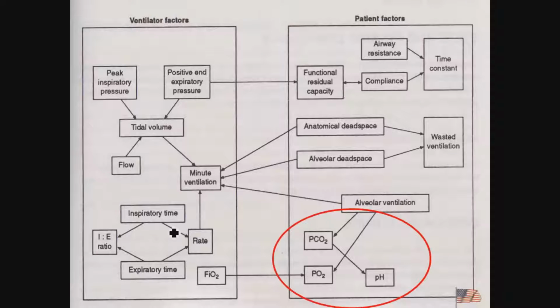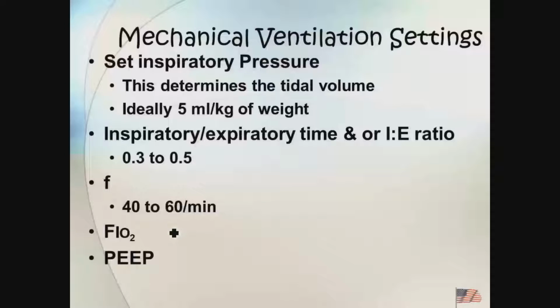So I want to alter my blood gases, and I'm going to do that by altering minute ventilation to control my CO2. We don't set tidal volume typically on infant ventilators. It's usually not something which is controlled by tidal volume, because we don't have a set tidal volume now. We're using a different type of ventilator, a pressure-based ventilator. And we can also use the rate to alter the minute ventilation. It's our primary mechanism by which we're going to control CO2, by controlling alveolar minute ventilation.